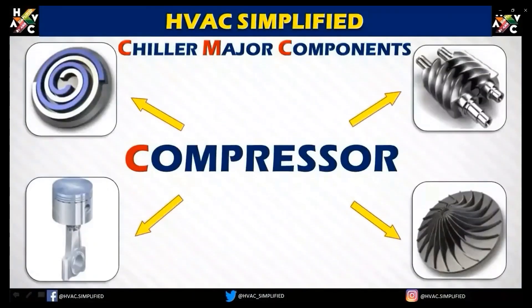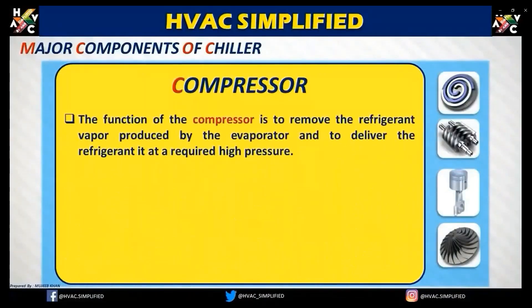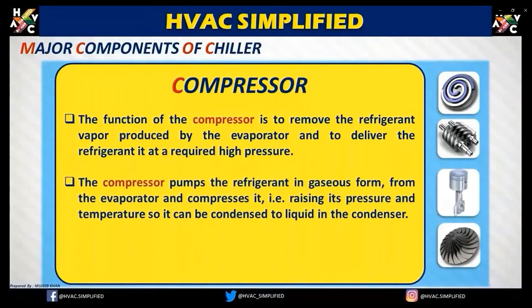The compressor is a major component, and there are four types. The function of the compressor is to remove the refrigerant vapor produced by the evaporator and deliver it at high pressure. The compressor pumps the refrigerant in gaseous form from the evaporator, compresses it — raising its pressure and temperature — so it can be condensed to a liquid in the condenser.